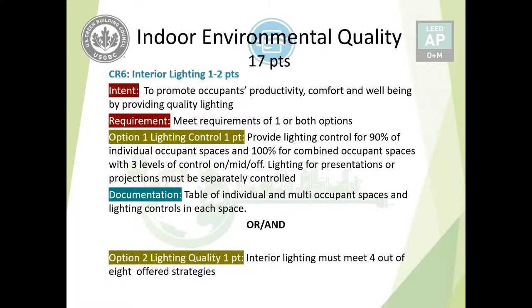Credit number 6 is Interior Lighting for one to two points. Option 1 provides one point by giving lighting controls to 90% of individual occupant spaces (such as single-person offices) and 100% of multi-occupant spaces (common work floors). Three levels of control must be provided — most buildings only offer on/off, so a third level is required to earn this credit. Lighting for presentation or projection rooms may be separately controlled or exempted. Documentation is a table of individual and multi-occupant spaces and the controls provided in each.